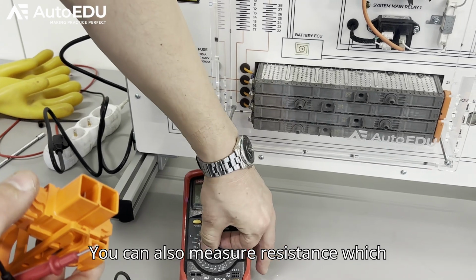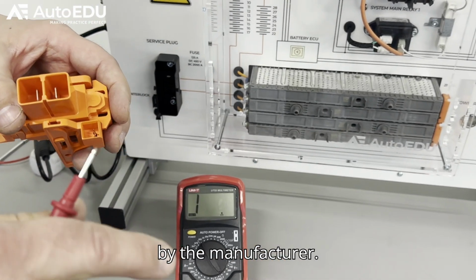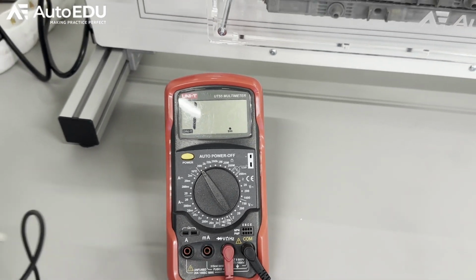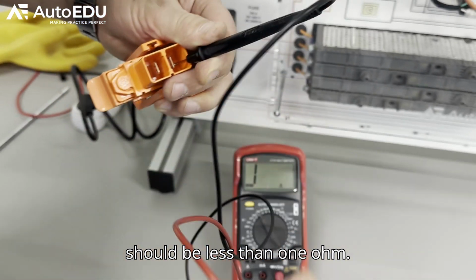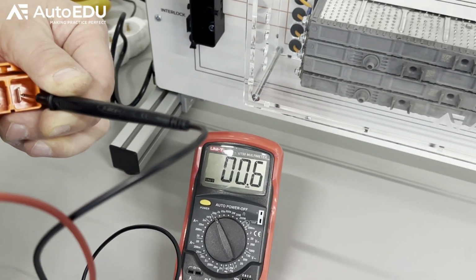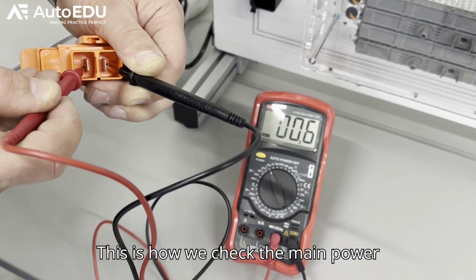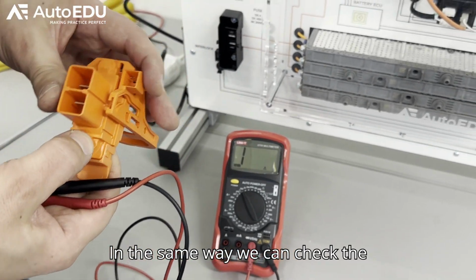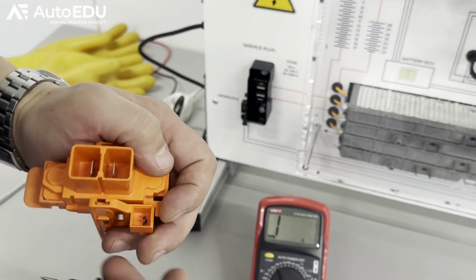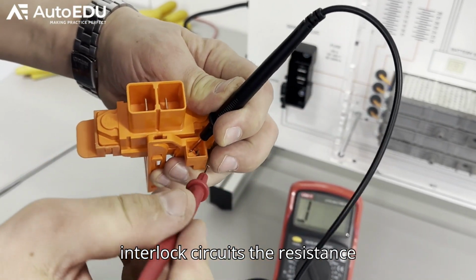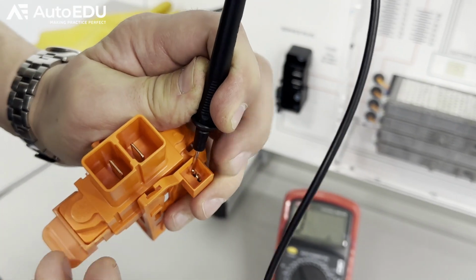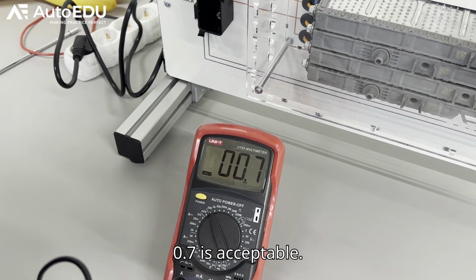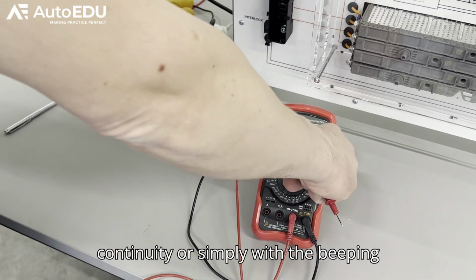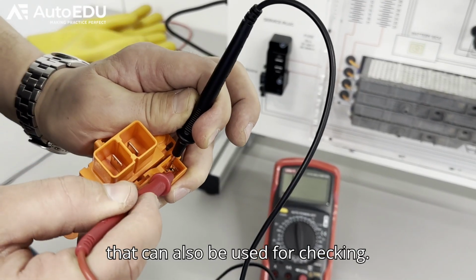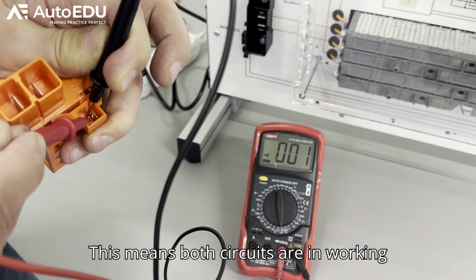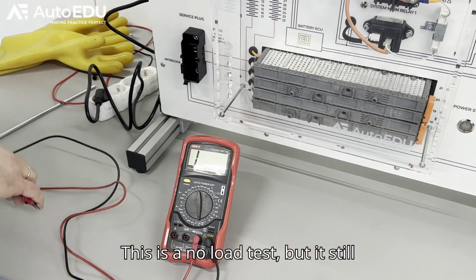You can also measure resistance, which should be less than 1 ohm, as declared by the manufacturer. We also set it to measure resistance, touch the contacts, and the resistance should be less than 1 ohm. This is how we check the main power contacts. In the same way, we can check the interlock too. Interlock circuits. The resistance must also be less than 1 ohm. 0.7 is acceptable. You can also check using circuit continuity, or simply with the beeping signal. That can also be used for checking. This means both circuits are in working order. This is a no-load test, but it still works.